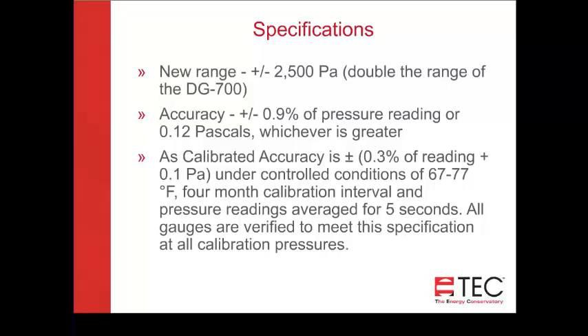So under laboratory conditions, 67 to 77 degrees, and using 5-second averages, the gauge is far more accurate. In other webinars, when we've talked about calibration of gauges, one of the things that takes effect is drift. One of the things that we know in our calculations is that after about 4 months, the average amount of drift will start to affect the instrument, and that will move us outside of this 0.3% of reading. But all of the gauges that leave here, whenever they're calibrated, either new or when they eventually start coming back for recalibration, are going to be verified to meet the specification at all calibration pressures. So this is truly a step-changing instrument in accuracy.